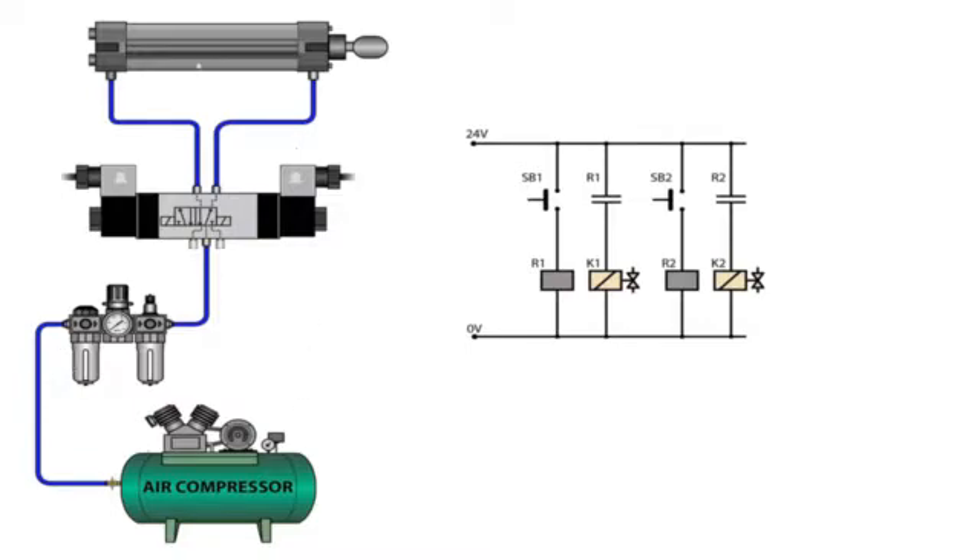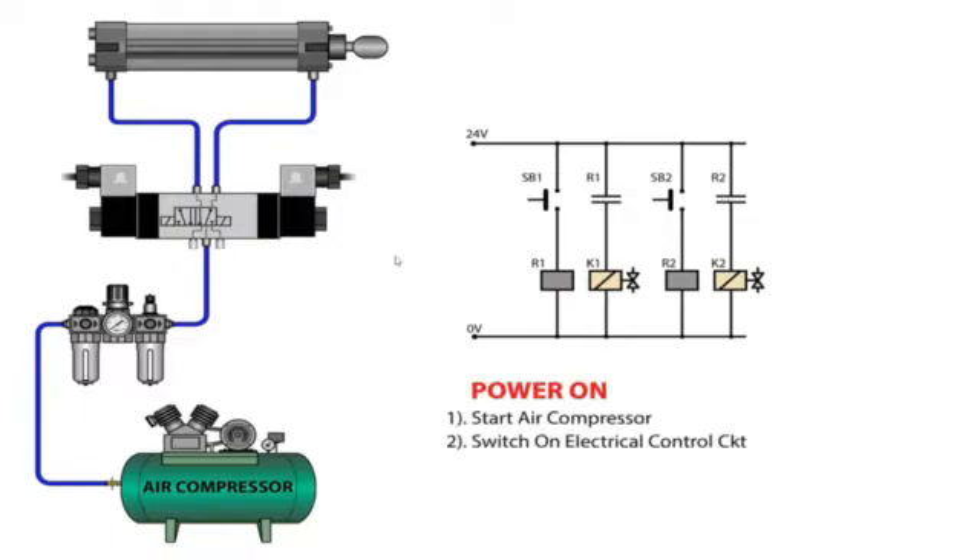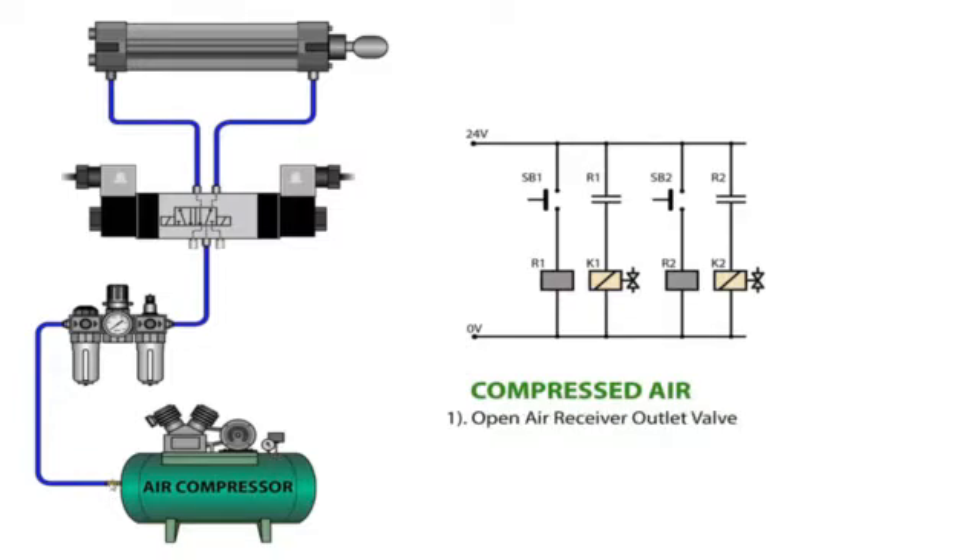On the starboard side we have the electrical control circuit. We have SB1, which is start button one, start button two, the relay, solenoid relay, solenoid two, and we have the normally open contacts R1 and R2. We will now simulate switching on the power — starting the air compressor and switching on the electrical control circuit. Through compressed air, we check the pressure gauge; there should be pressure inside the receiving tank. We open the valve so control air passes through the filter, regulator, and lubricator.